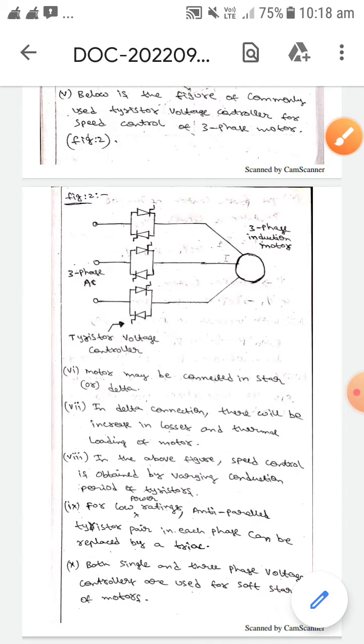In this, the motor can be connected in star or delta. In delta connection there will be increase in losses and thermal loading of motor. In the above figure, speed control is obtained by varying the conduction period of these thyristors.